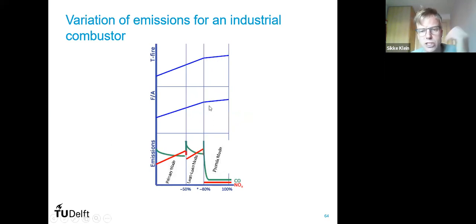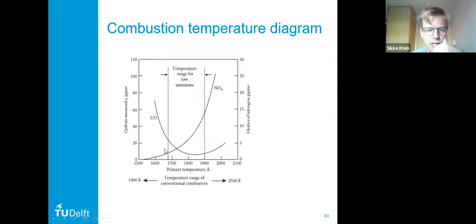In this situation, typically for the older gas turbines, you can only run in premixed mode above 80% operation. Here you control the air mass flow by the IGVs, and this way have a constant turbine inlet temperature and flame temperature. At lower flame temperatures, if you go further to part load, you decrease the flame temperature, and you go to the left in this diagram. Then you enter unstable combustion. So you have high CO. The high CO is the first indication, but it means incomplete combustion, so you don't get any combustion reaction anymore.